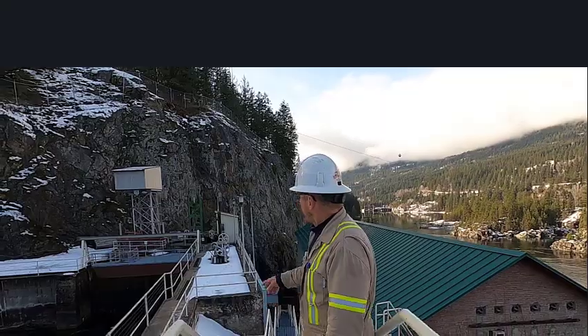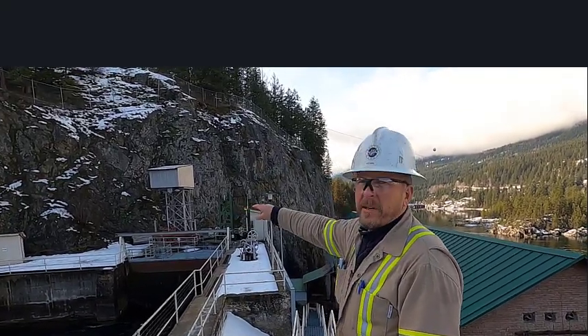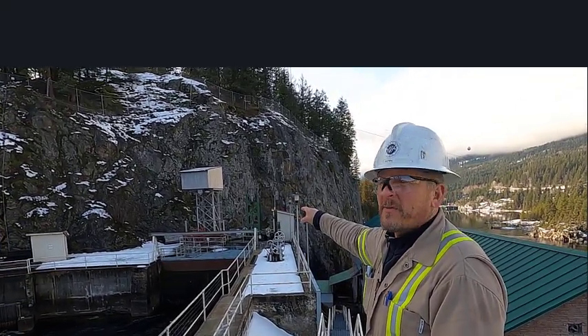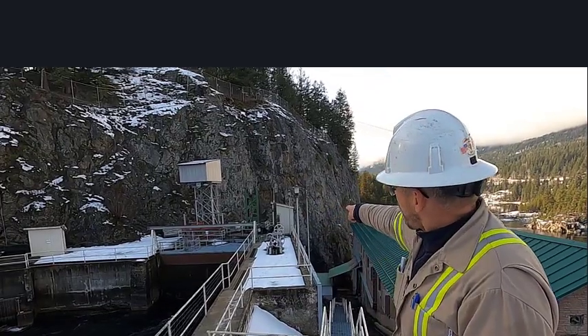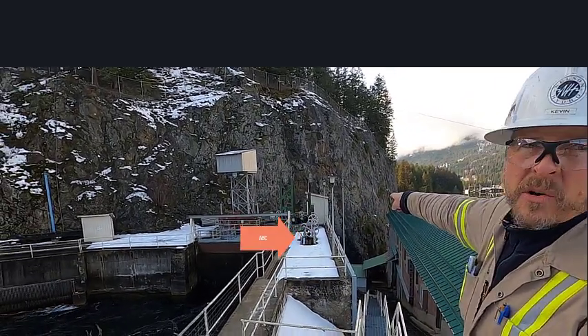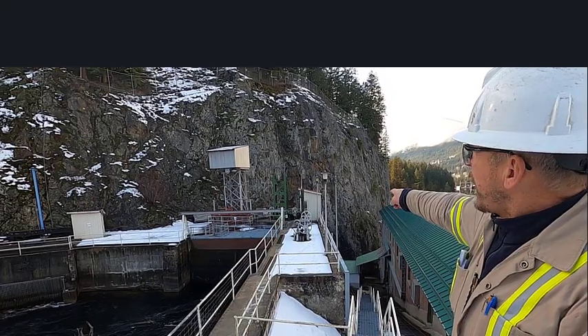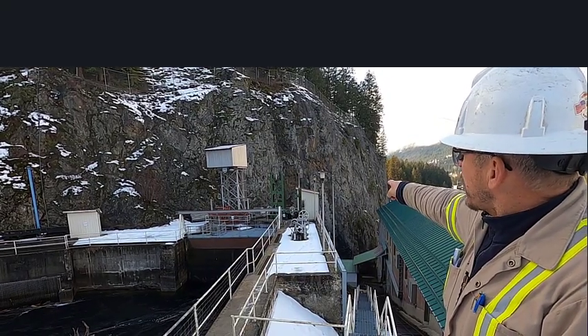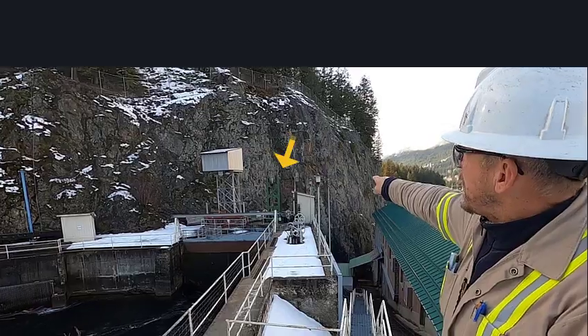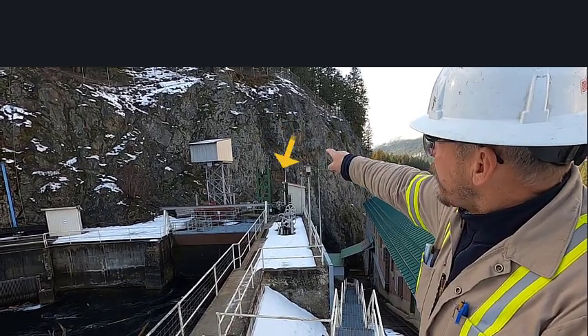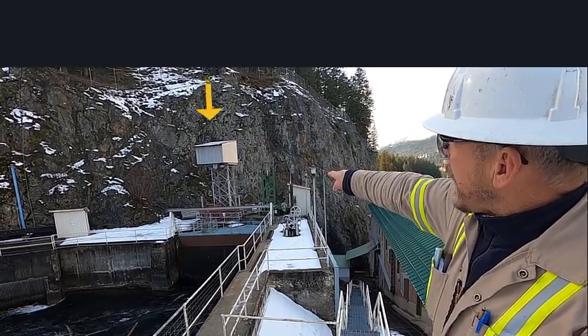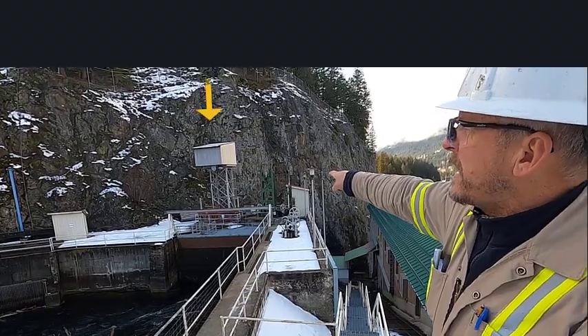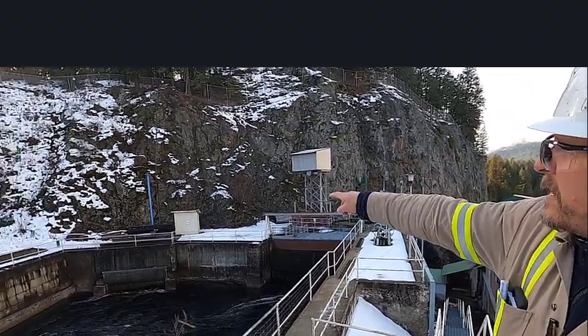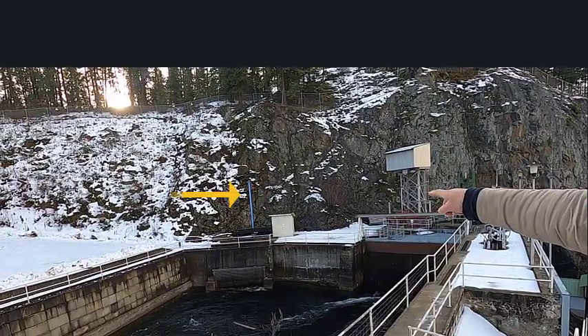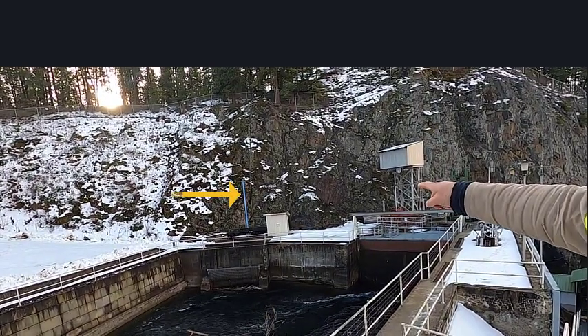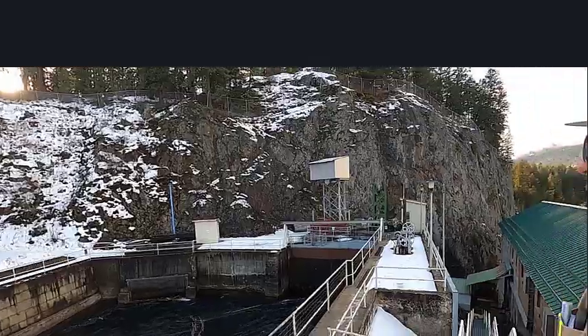Okay, we're still at the forebay here. So each one of the generator units has a gate, basically for maintenance. So starting over here, there's a silver gate. That's our oldest unit that hasn't actually ran since the 1970s, but next to it are 2 older units, there's 2 green gates. And then the third guy there is a silver gate that was installed in 1950. And then over to the left here is another gate, which is actually hydraulically operated. That's for unit 5 that was installed in 1995.